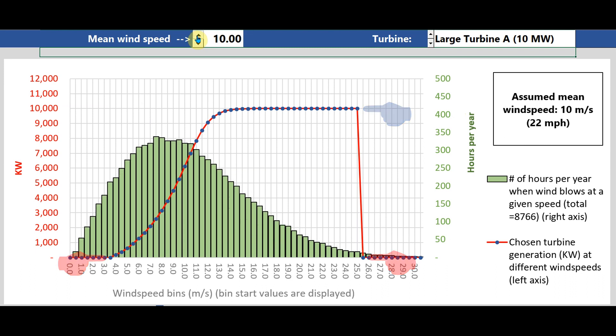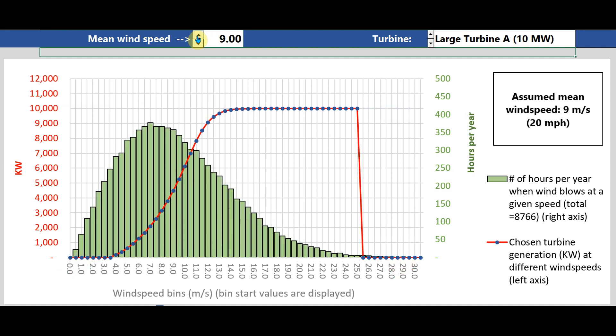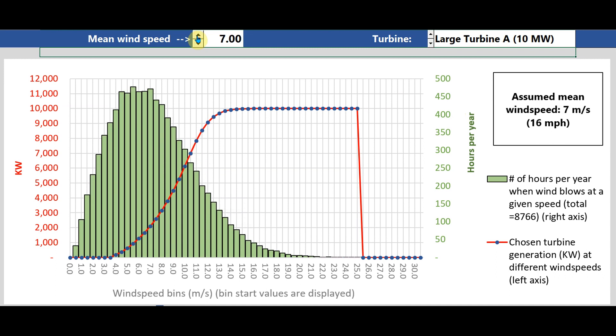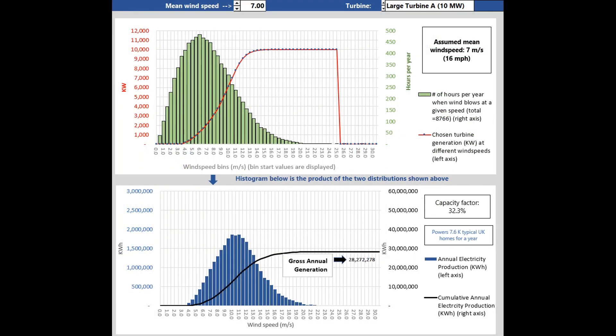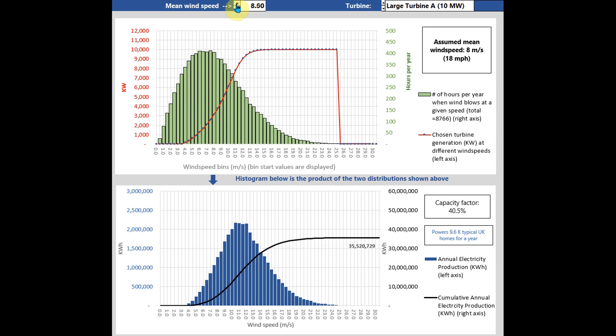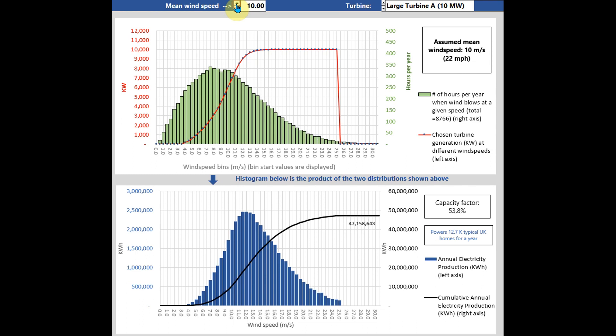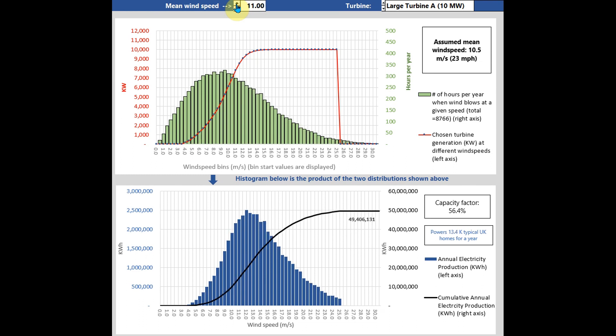Ideally, you'd want all of it to be at the higher speeds, which correspond to the maximum generation plateau. Once you have these two lined up, it's one simple math step to get what matters: gross annual generation — a shorthand term for AEP — shown by the data label at the end of the black line. When the mean wind speed increases, it makes intuitive sense, but it's really nice to be able to quantify it from first principles.